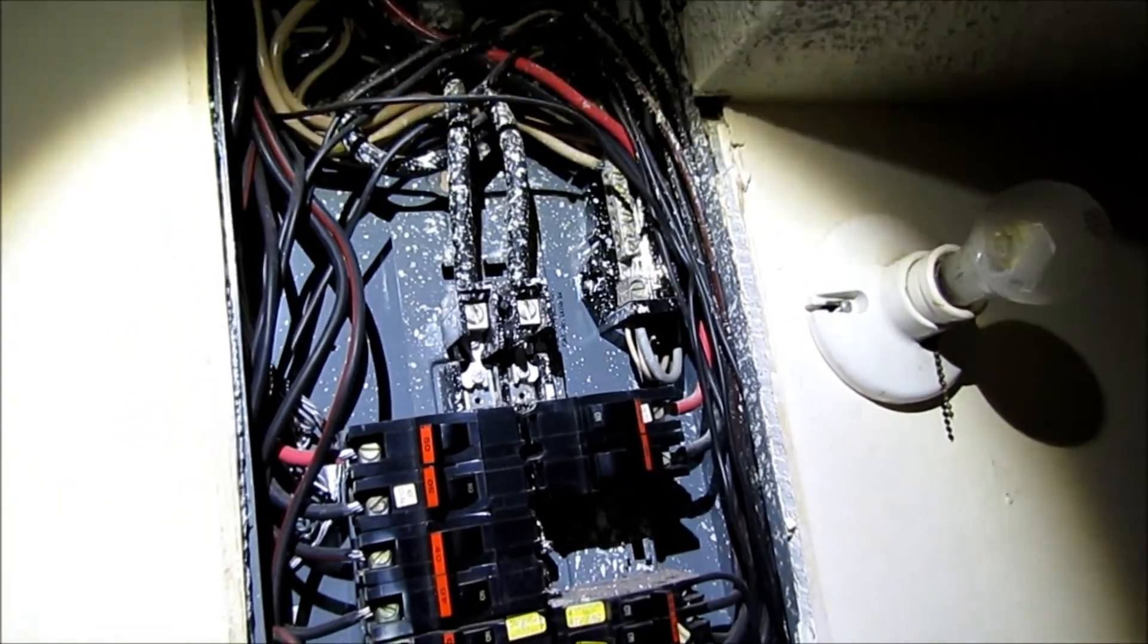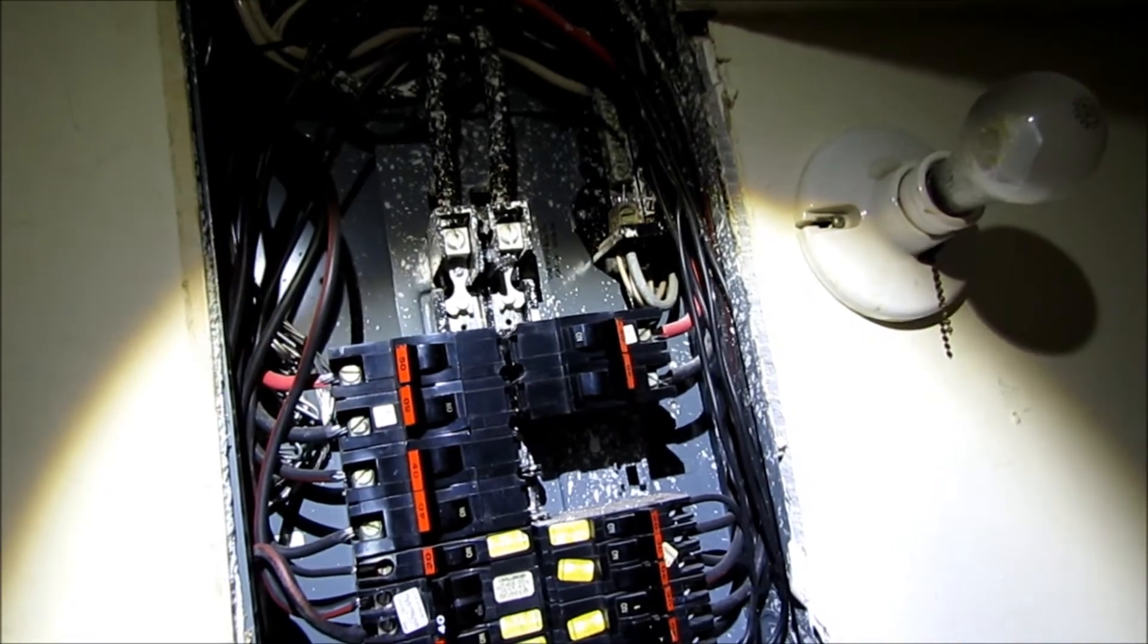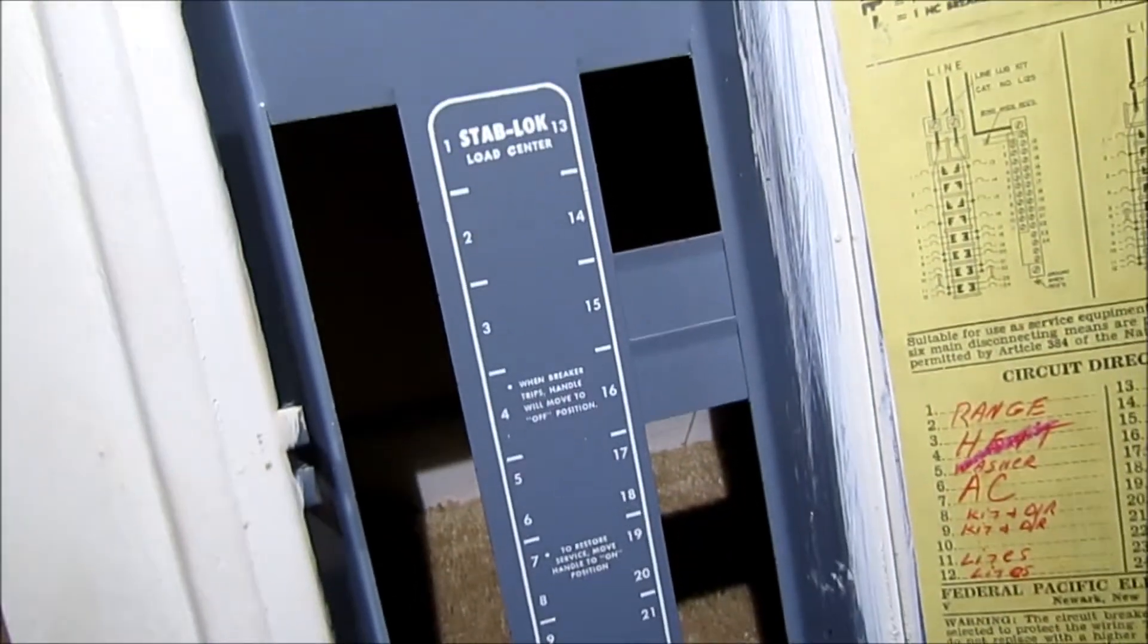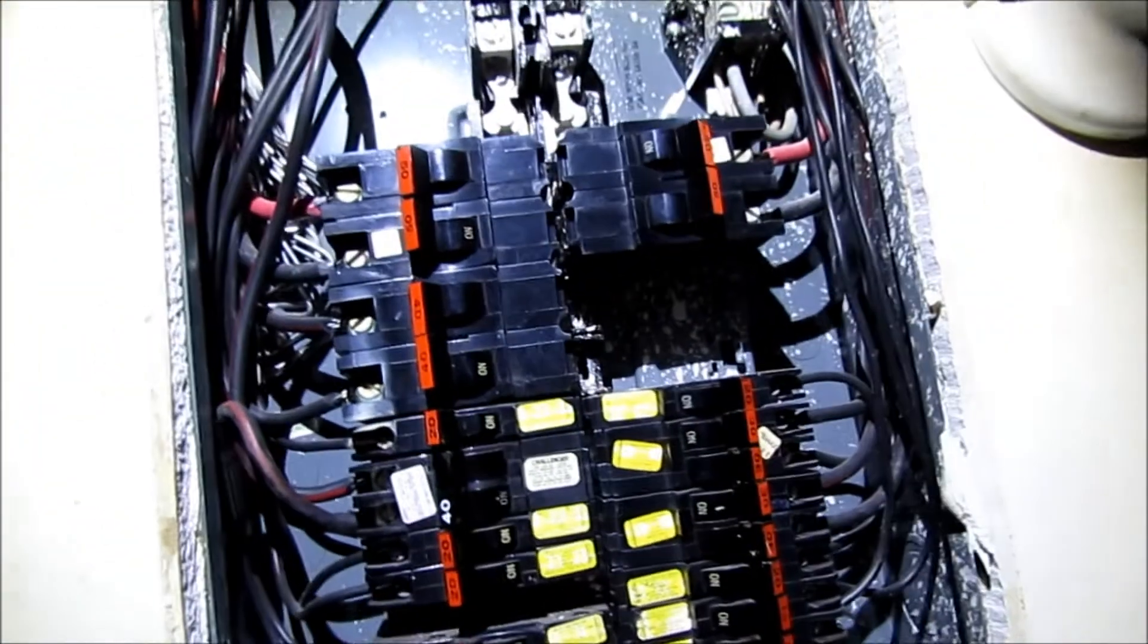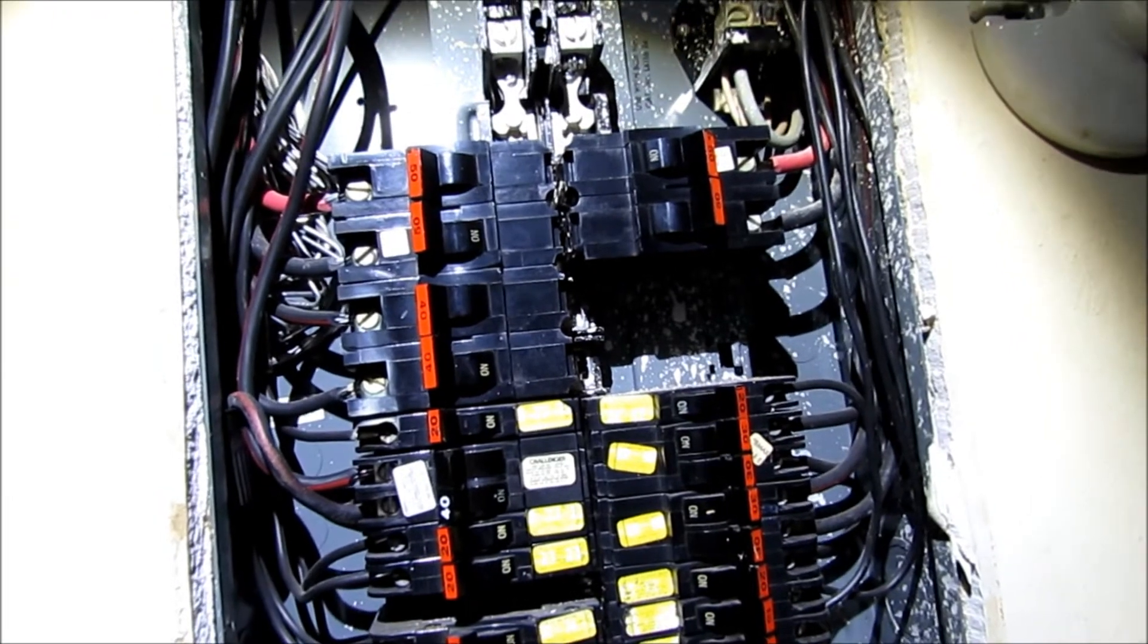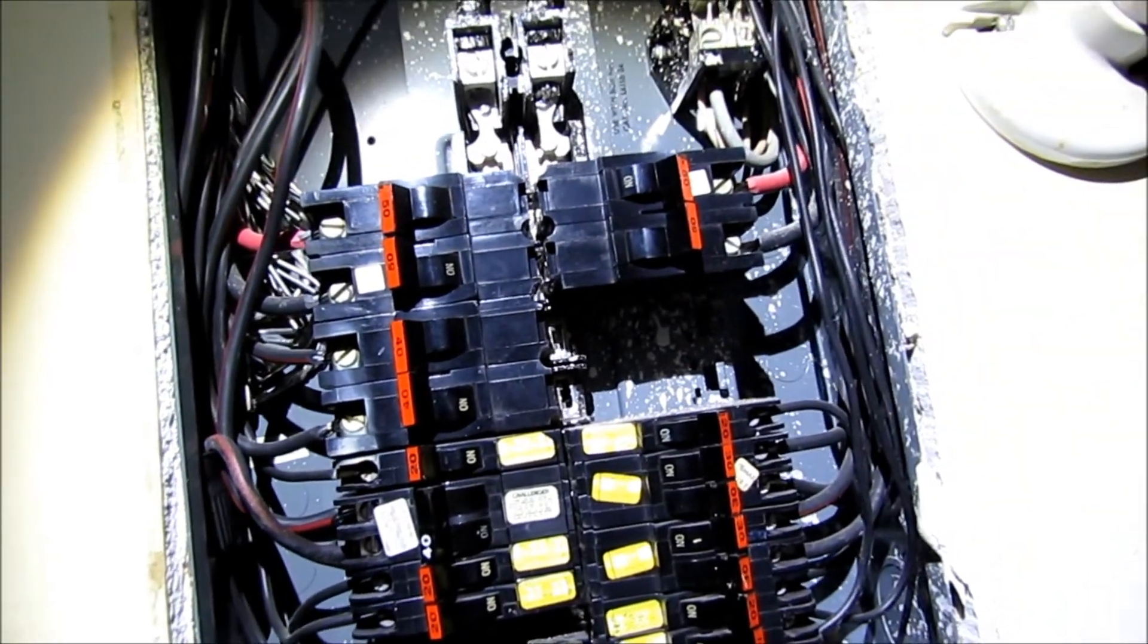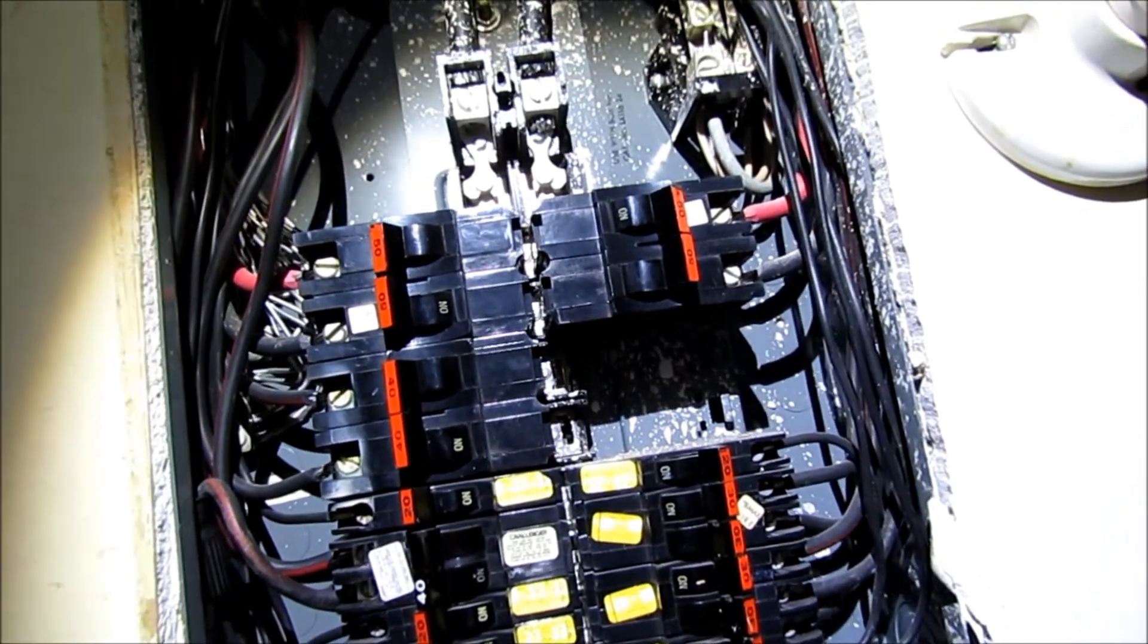But this also has more issues than just the aluminum wire. This panel is a Federal-Pacific Stab-Lok panel and it has reported issues - some of those issues that have been reported is that it's a potential fire hazard and that sometimes the breakers won't trip when they reach a fault status.